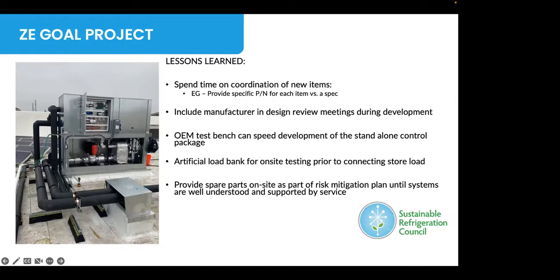We were able to fine tune the operation and ensure the chiller was going to perform, and had a lot more confidence that as we went into changing out the display cases, any of the initial bugs had been worked out with the system. That really enabled a pretty clean startup. Once all the cases were in place, the system started up successfully and has been maintaining good product temperatures along the way.